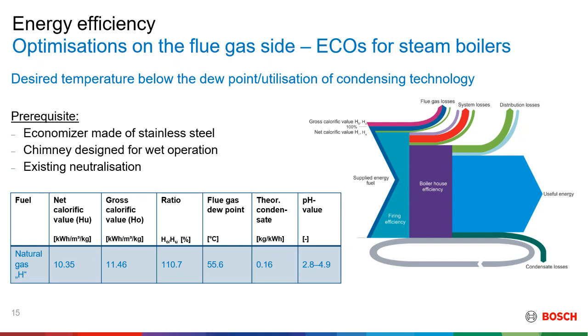What we have currently on the screen is a chart showing energy usage inside a boiler. Condensation losses, which is the first one, is usually quite tricky to utilize, depending on the fuel that you're using. Useful energy, that is quite good. Distribution losses depend on how you've cladded your pipes, how well the boiler is cladded, and so on. Then you have the system losses, inside the boiler, and then the flue gas losses. As we go forward, I'll try to explain how we can recover a majority of the losses and turn them into useful energy.